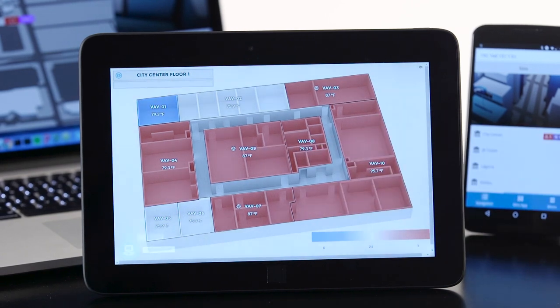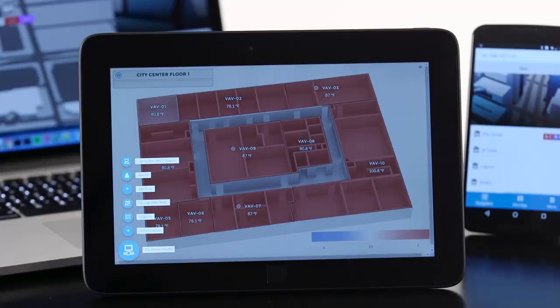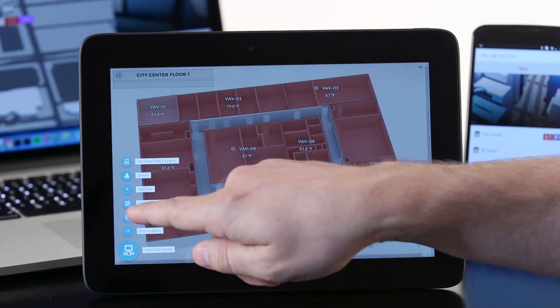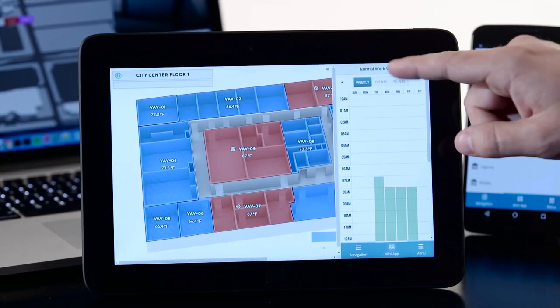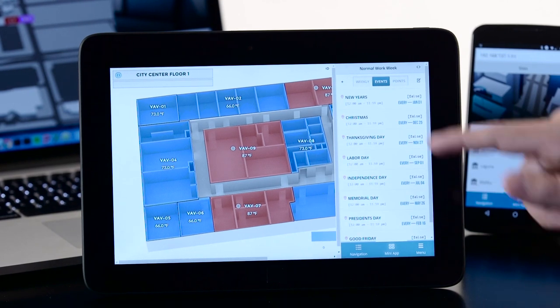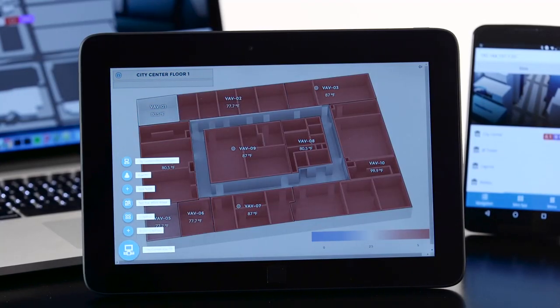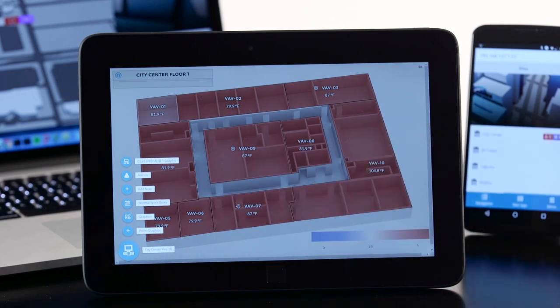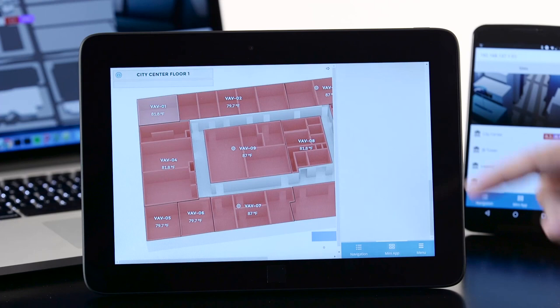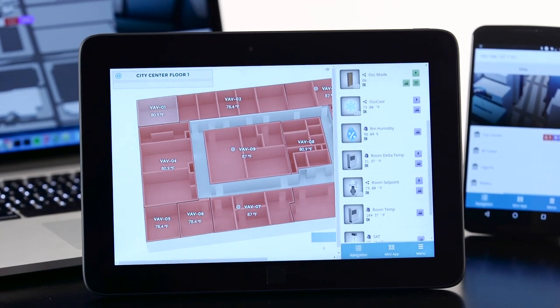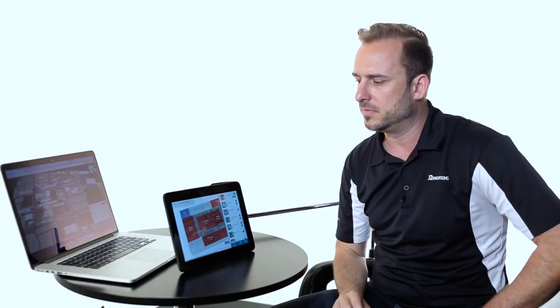Notice how the magic bubbles opened up on the left side so that when you're on a tablet or a phone, you could use your fingers. Now we're looking at the floor plan and let's drill down to a VAV box. The magic bubbles automatically show everything that's related to this VAV box. Let's edit a schedule — you can see that this VAV box is associated with the normal week schedule. I could go into the events and see what events are there, and also see all the points being controlled by that particular schedule. When I click on a different VAV box, the magic bubbles are dynamic — if there's an alarm, it'll show a magic bubble for the alarm; if there's a schedule, it'll show the schedule. None of this was engineered — the magic bubbles automatically work based on tags.